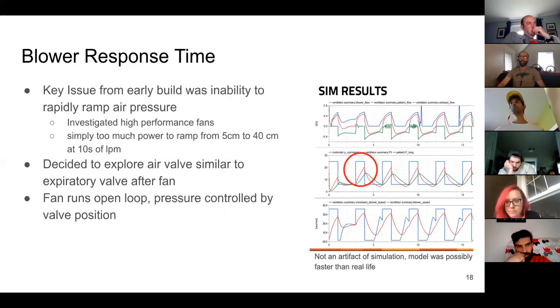As talked about in the previous slides, the fan here is going to run open loop, so the pressure is controlled by the valve position while the fan runs open loop. We could theoretically get a faster response by running both closed loop, but that gets into a significantly trickier dynamics controls problem that we didn't want to tackle right now. That's a potential down-the-line architecture to explore, but right now we're going to try to keep things simple to keep things from breaking.